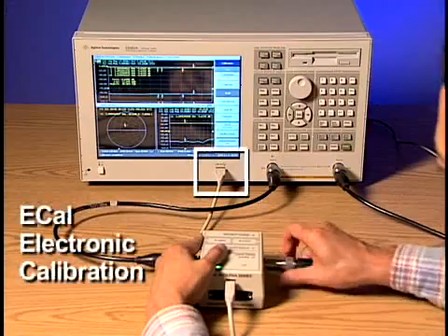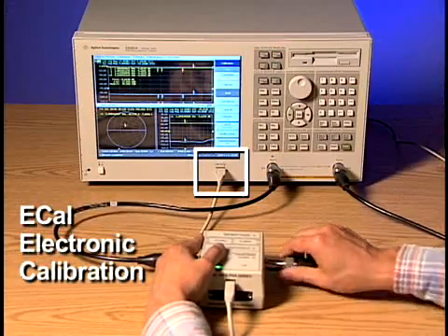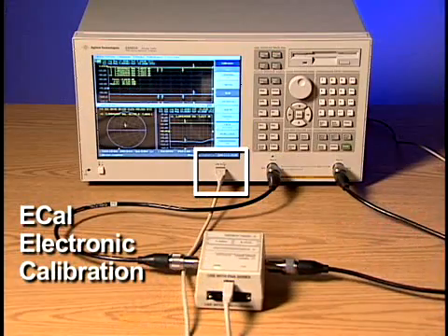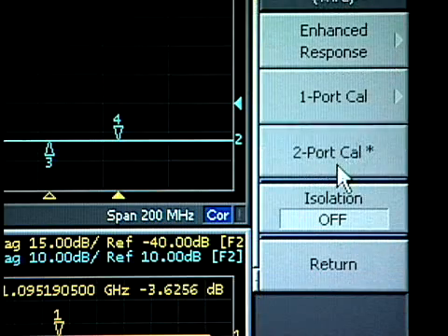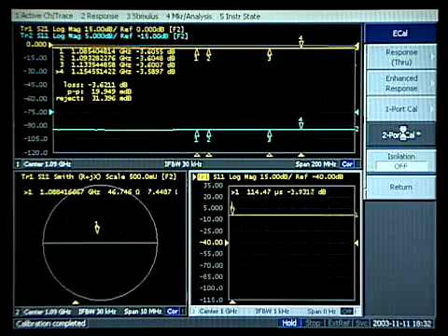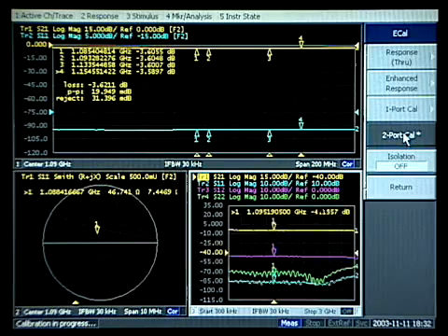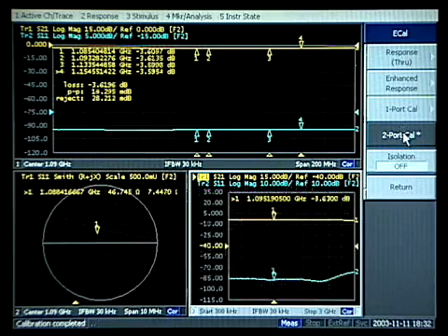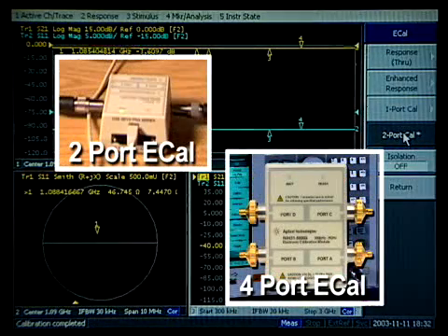Another time saver is ECAL, which replaces the time and complexity of manual calibration with much quicker and more accurate electronic calibration. ECALs are available at both 50 and 75-ohm, with two- and four-port options.